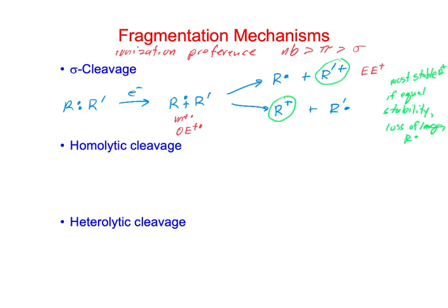Does it go out from the instrument? Yeah, the radicals, because remember in EI, we're doing this under high vacuum. We have a vacuum pump that's pumping it out. So anything that we don't observe, there can be other things formed. We could have anions that are formed in the process or neutral species. Any of those will just be pumped out. And only the cations get accelerated down the flight tube. Well, all of the cations will be accelerated. They will all be observed.